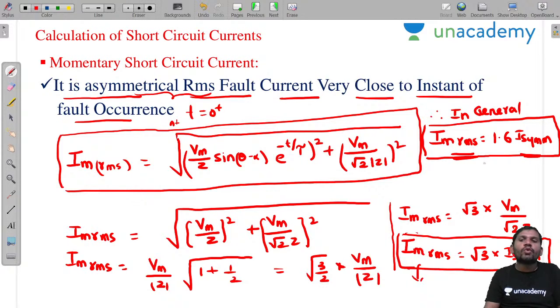So Im RMS equals 1.6 times the symmetrical current. If there is no DC component, we consider Vm by Z. This 1.732 figure comes from an approximate analysis, a theoretical calculation, but practically you take Im RMS, the momentary short circuit current RMS value, as 1.6 times the symmetrical current.